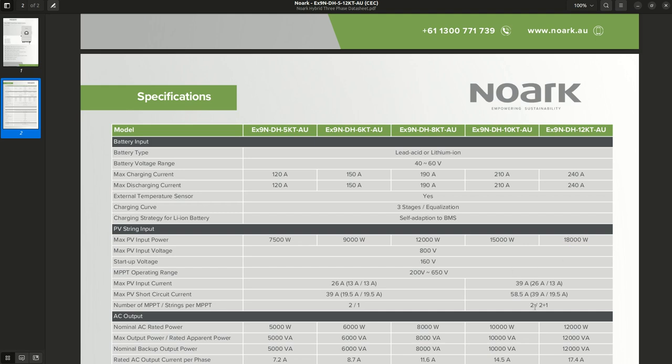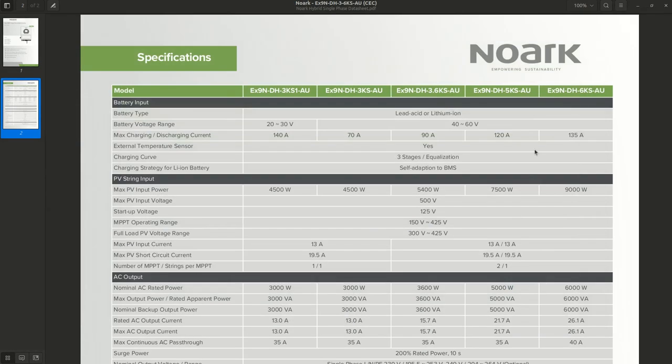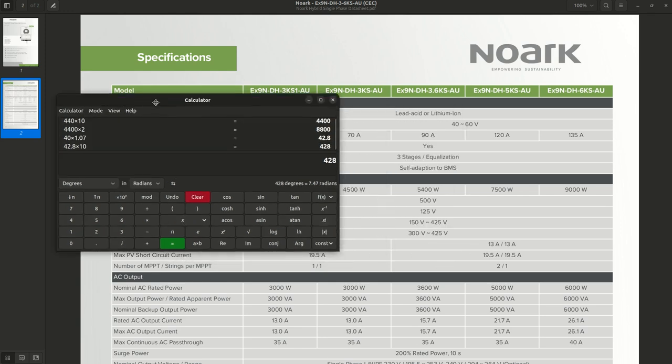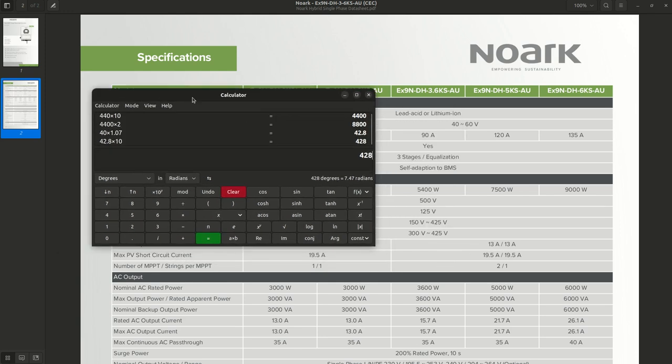However, what I didn't look at was the 500 volt limit on the 6 kilowatt model, which is kind of low. I've got to admit, I'm quite surprised. That's why I missed it, because I've never seen that before. I've seen 580 volts at lowest.